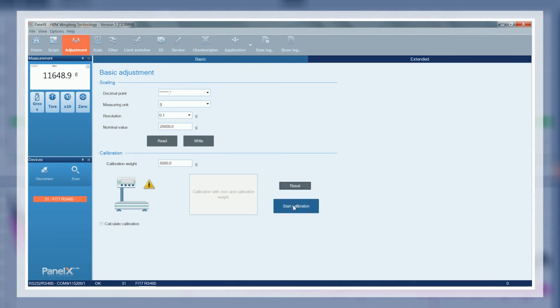Start Calibration to initiate the weight calibration. The software issues the prompt "No Load on Scale, Click Measure," asking us to remove any loads from the load conveyor. We're then prompted to click Measure 0 to calibrate the zero weight of the conveyor. We'll do just that, and a message "Calibration Weight on Scale, Click Measure" will appear, prompting us to enter the calibration weight on the conveyor.